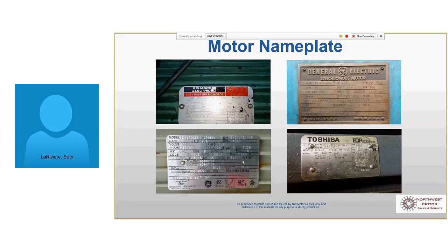Not everybody does. I was down at a customer site last week where the guy was having a hard time identifying what bearings go in the motor, and so I was helping him do that and realized, wow, none of them are marked. That's unusual because I'm used to working with GE and we always put the model numbers, the bearing part numbers on the nameplate.